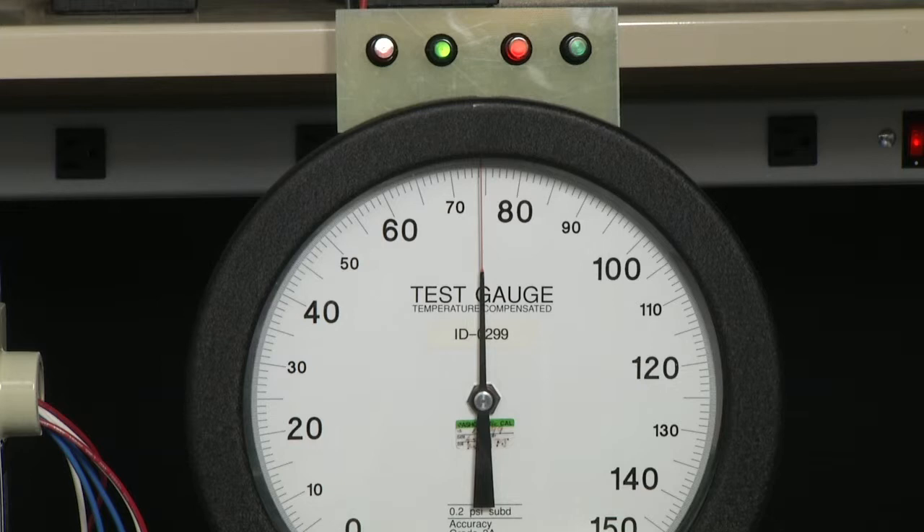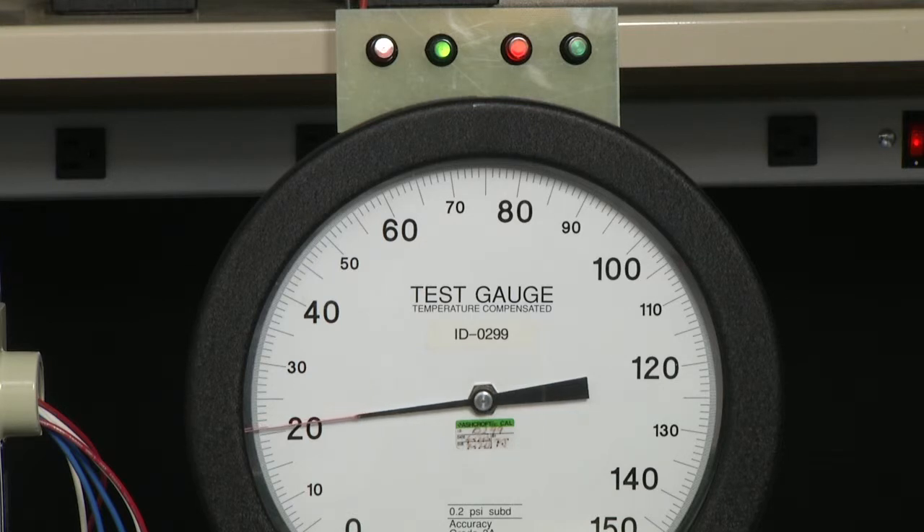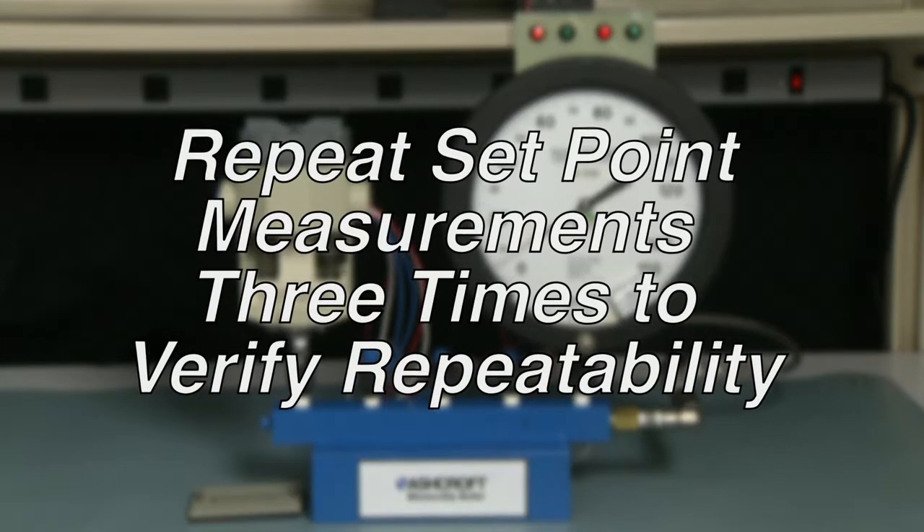Now we're going to go down to the 20 psi set point, the decreasing set point. We'll get close and move it slowly. We're at 20 psi. Now we're going to increase it to measure the set point of the A switch — it's approximately 23 psi. So the A side has a dead band of 3 and the B side had a dead band of five. We would now go back to zero and repeat this measurement three times for accuracy.